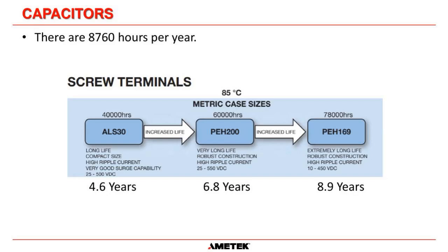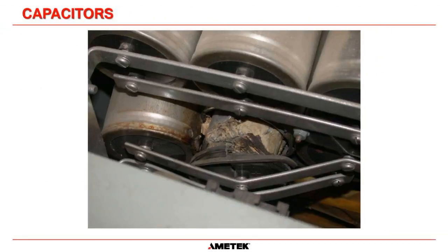Now, if you don't replace the capacitors, this can be what happens. And this is a very good example of how much force is available in a capacitor that fails. You can see that you have a bus bar here. This is what it should look like. So this bus bar should be running parallel to those top bus bars. But obviously, this bottom middle capacitor here has failed.